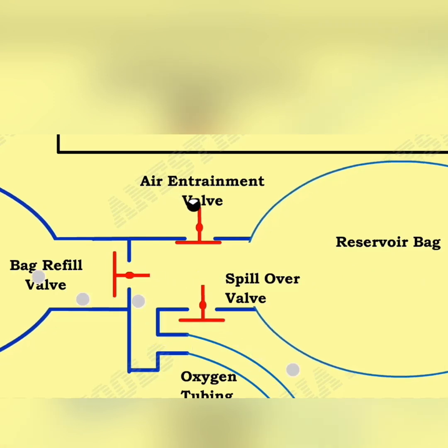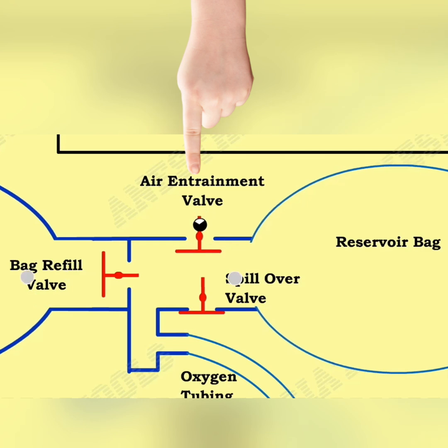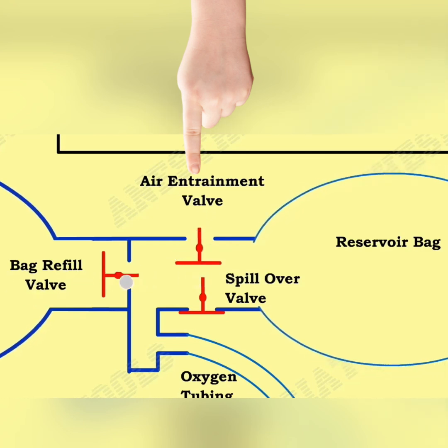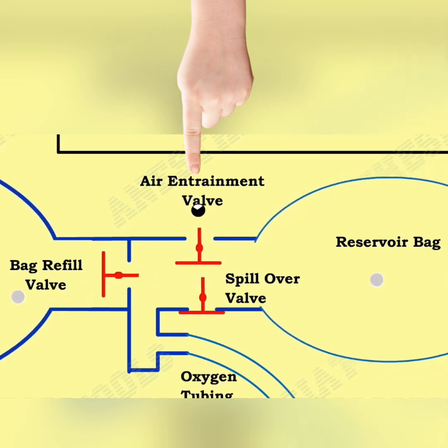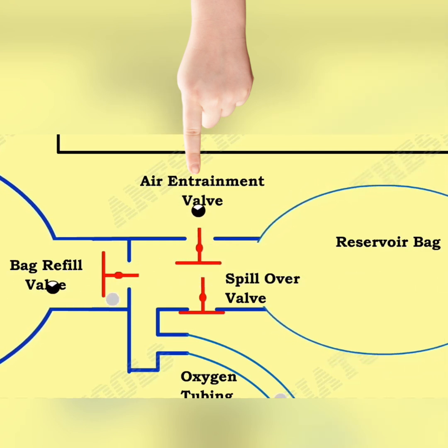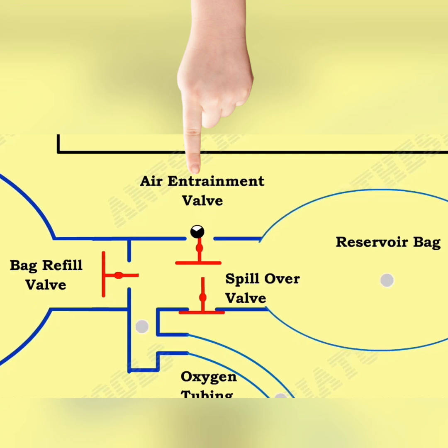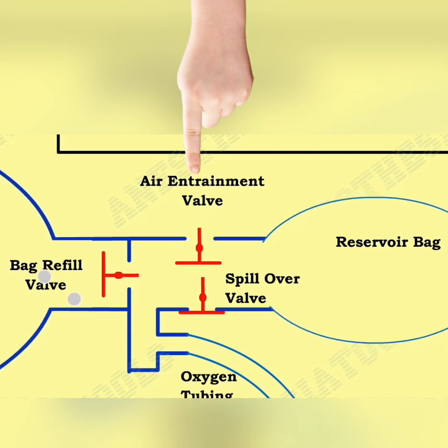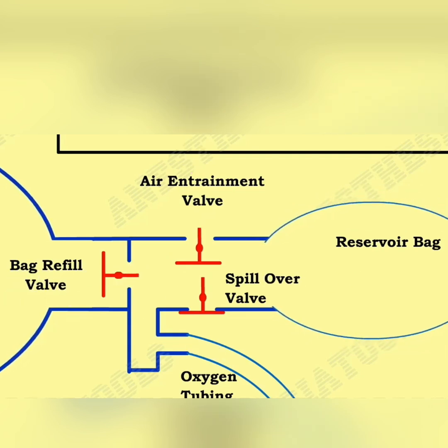When excess inflow demand is there which cannot be met by the oxygen tubing or the reservoir bag, the air entrainment valve opens allowing air to get into the self-inflating bag through the bag refill valve.